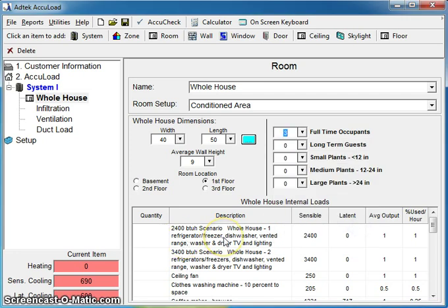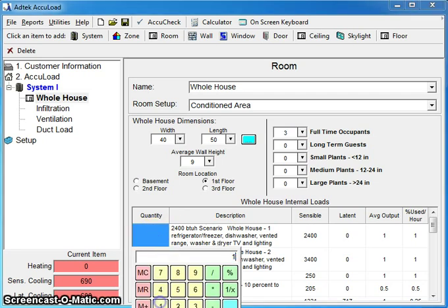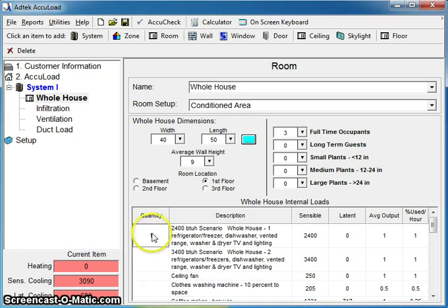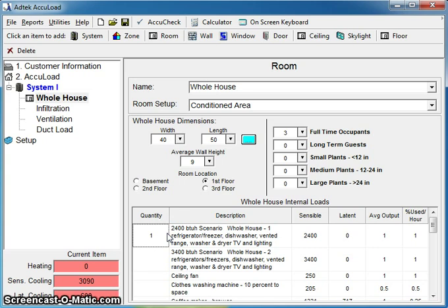Down here at the bottom, you're going to see a bunch of different internal loads. Appliances, refrigerators, freezers. According to Manual J, we're going to put in a quantity of one. The 2400 BTU scenario takes care of the consistent appliances that are constantly running. The fridges, the freezers, some average TV and lighting. That's what you'll do on just about every whole house scenario you're doing.